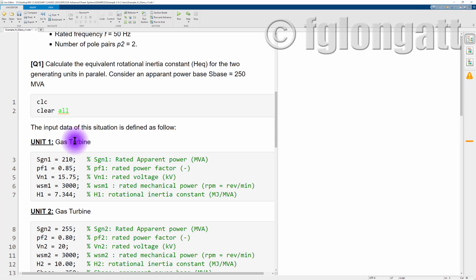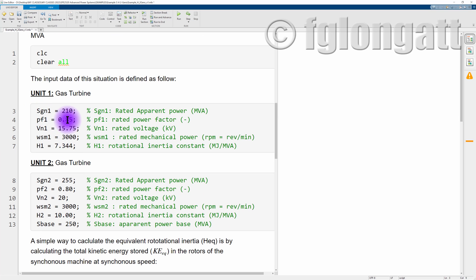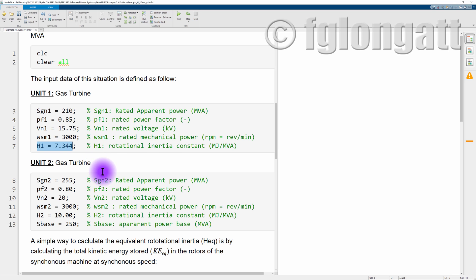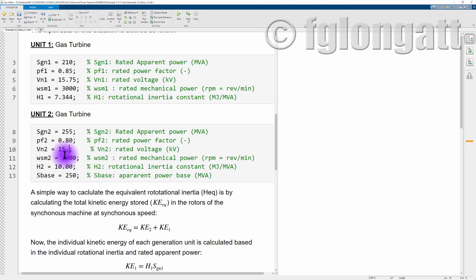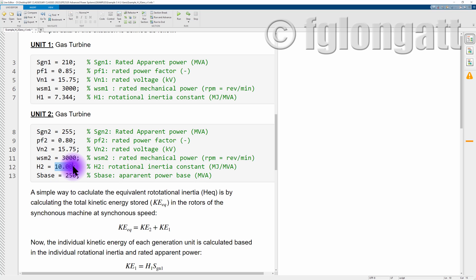Now we clear the screen and set up the input data. Unit one: 210 MVA, power factor 0.85, 3000 RPM, rotational inertia constant H1 = 7.344 MJ/MVA. Unit two: 255 MVA, power factor 0.8, voltage 15.75 kV, 3000 RPM, inertia constant H2 = 10 megajoules per MVA. The base power is 250 MVA.